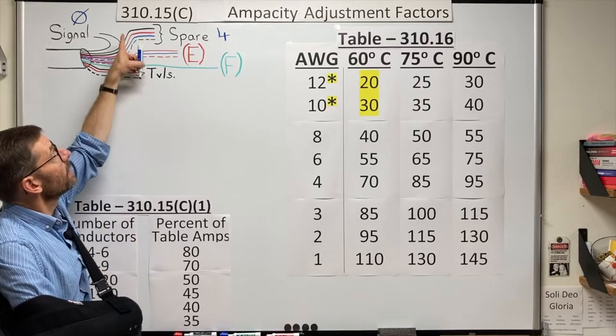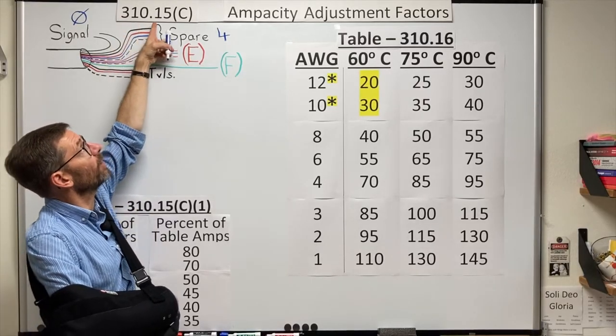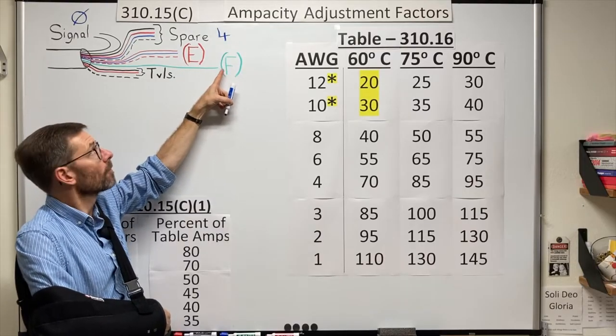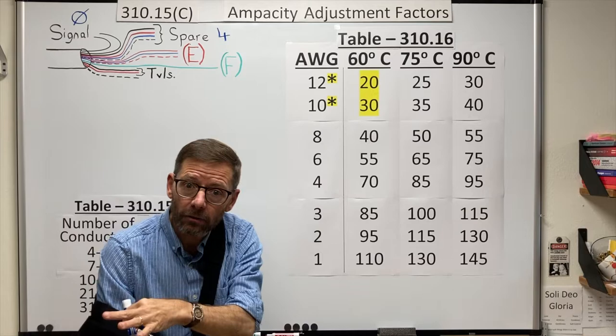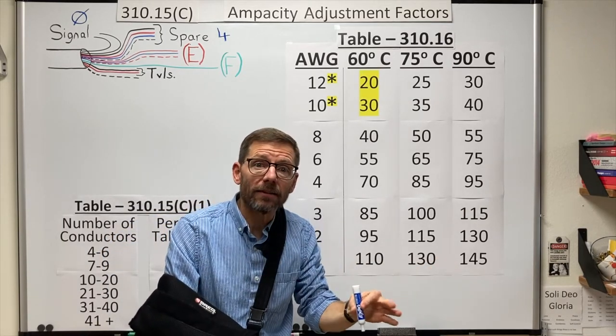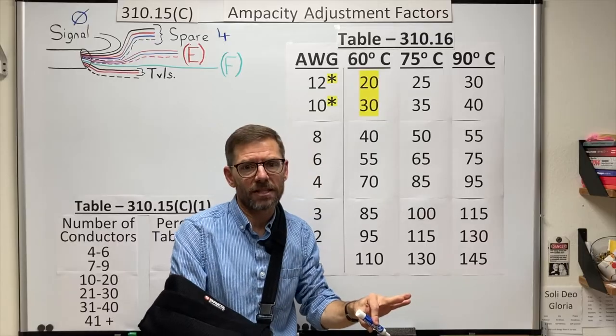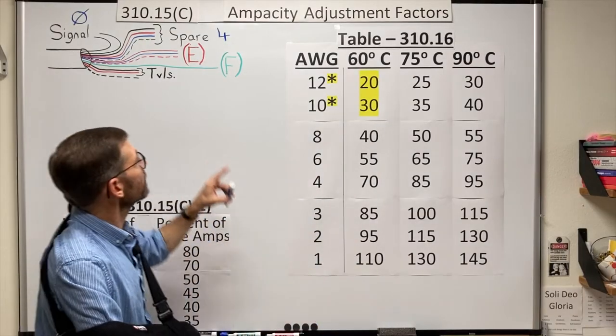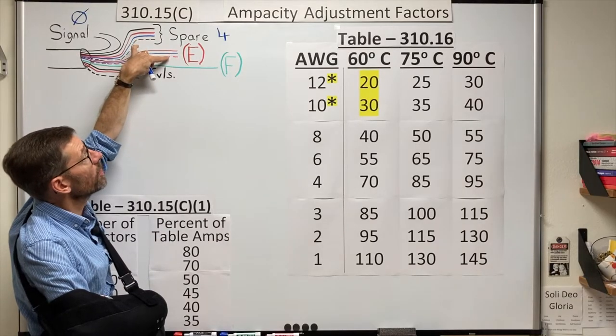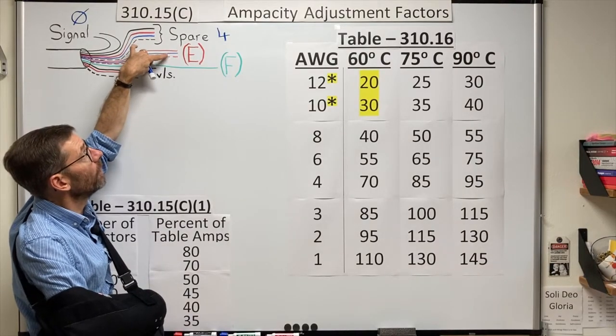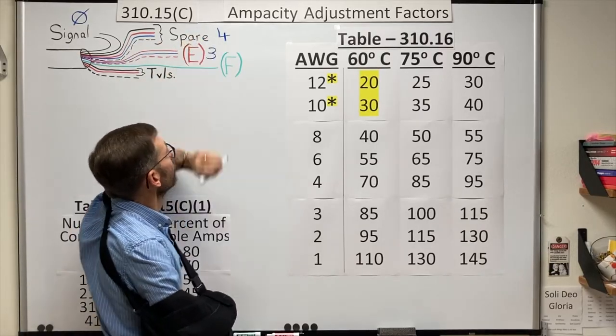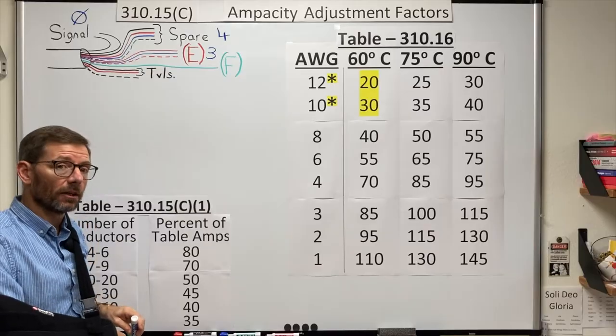The second sentence tells me to look at 310.15(E) and (F). Now E answers the question, do I count the neutral or not? I have another video on that to talk about the specifics of that section. But for now, let's just say here, if I have two phases of a three-phase system with a shared neutral, I would need to count all of them, the neutral included. So here I have three current-carrying conductors.